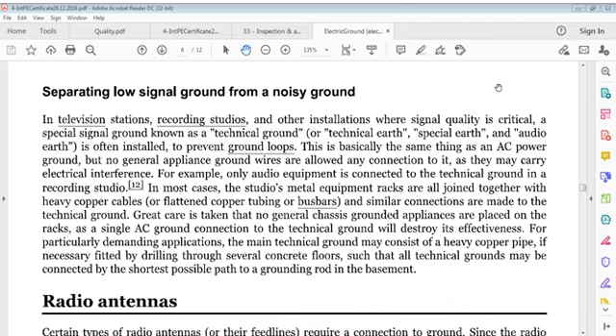For particularly demanding applications, main technical ground may consist of a heavy copper pipe, if necessary fitted by drilling through several concrete floors, such that all technical grounds may be connected by the shortest possible path to a grounding rod in the basement.